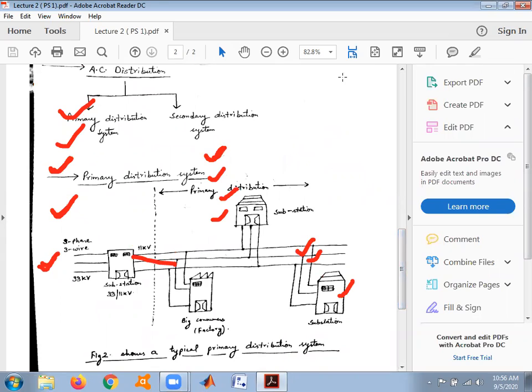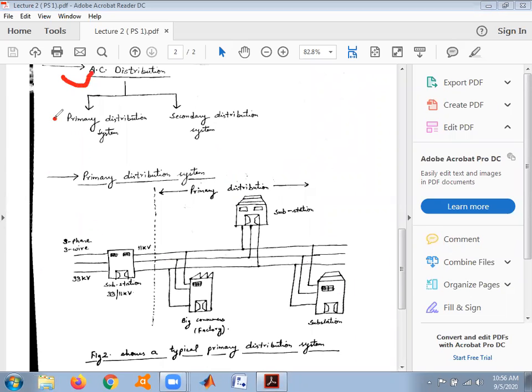When we discuss the AC distribution system, it is divided into two categories: primary distribution system and secondary distribution system. In primary distribution system, the incoming to the substation is 3-phase 3-wire, meaning 33 kV or 11 kV. So it's 33 kV at the receiving end and 11 kV at the sending end. There is a distribution transformer installed inside the substation which converts 33 kV to 11 kV.